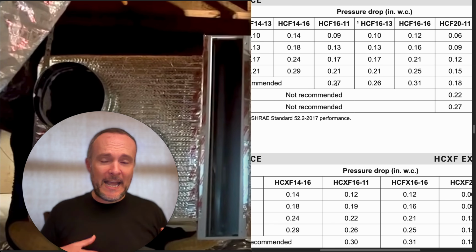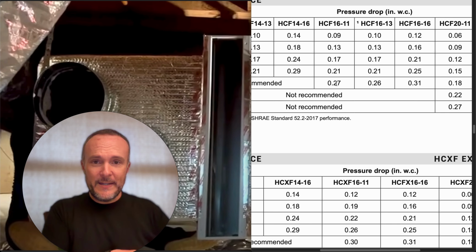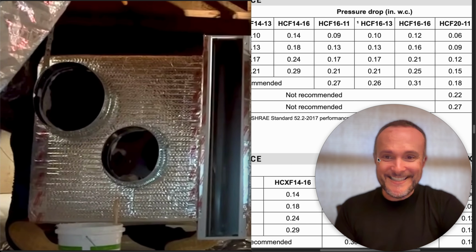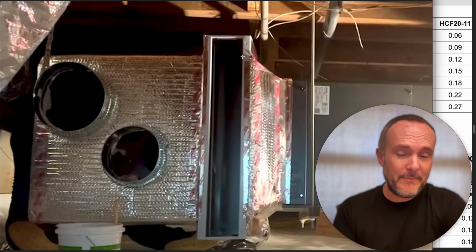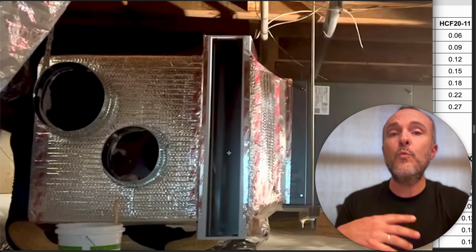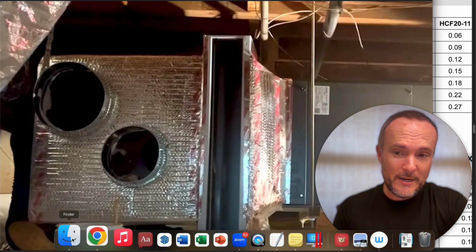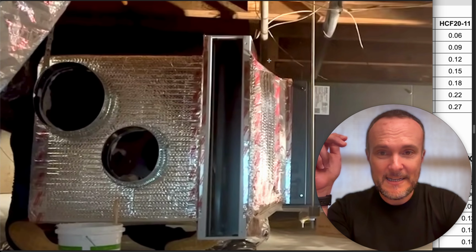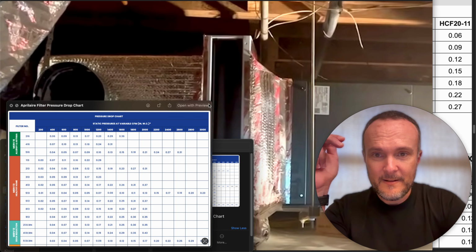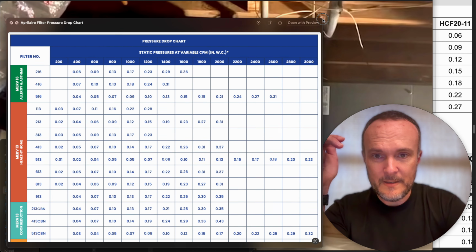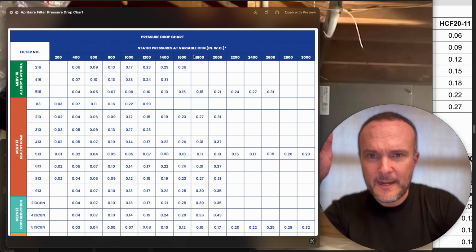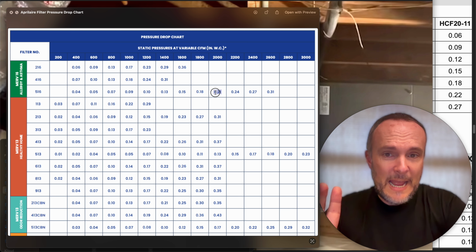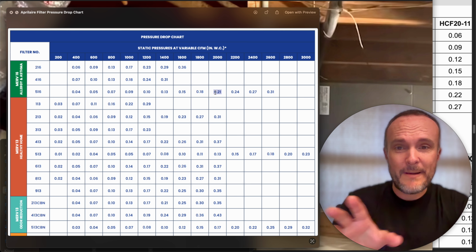You have to take that thing out, cut it out, throw it away, and then you're gonna have to get something. And my thinking is, hey, if you're going to get something, why don't you get something that's gigantic? Then you can do whatever you want with it.